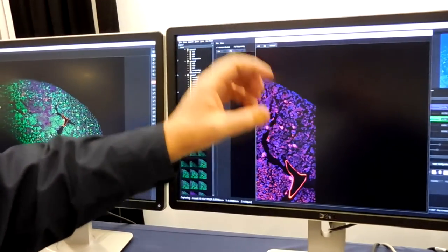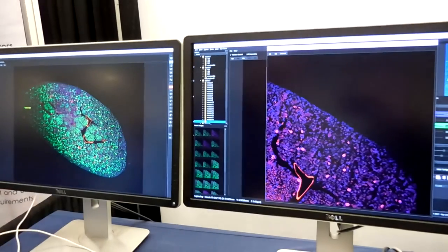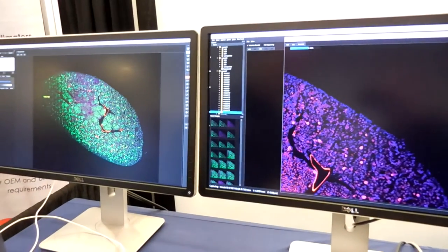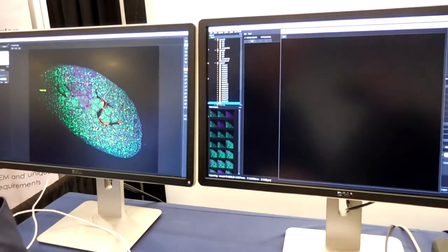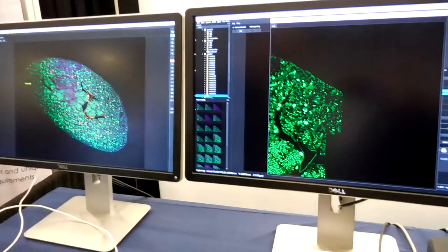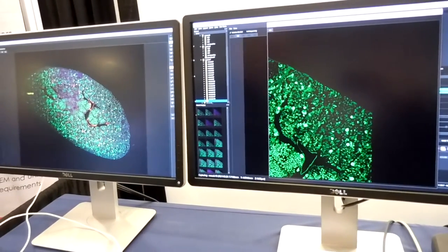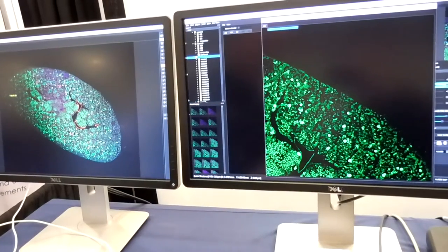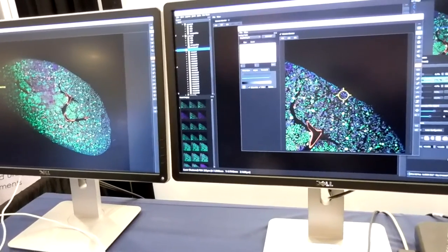The unit has two detectors so we do two colors simultaneously. As you can see, each tile is imaged, acquired, and then stitched to the previous one. After a few rows, we stitch the strips together, and when done we do a complete seam carve using pixel recognition software to get the best fit. That completes the first two colors. Now it's coming back to repeat for the final color, which is an Alexa 488 GFP signal. After this, it'll do a quick seam carve and combine the images into our finished product.